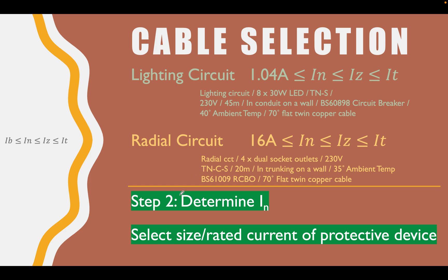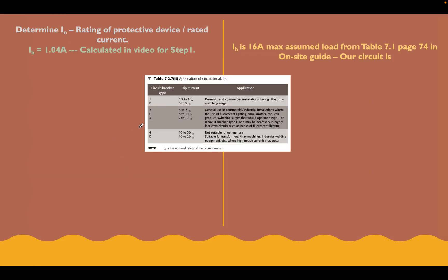Let's go to step 2. Determine IN, select the size or current rating of our protective device. We've got this table in the middle, we'll go through this afterwards. Let's just look at these two circuits and select our devices. We know to start with that this is always true - this is part of our formula we just looked at and we just spoke about. The rating of our protective device, our IN, has to be greater or equal to our design current.